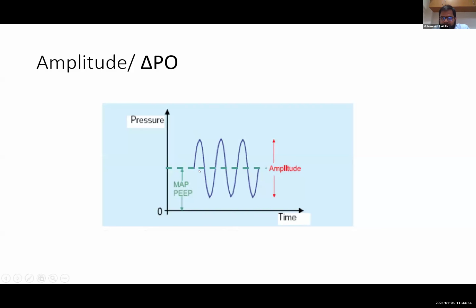depending on the TI time, the negative pressures will be less. If the IE time is more, then this pressure might be less, the delivered pressure during the expiration. So this will determine your amplitude. But as you see, the amplitude which was generated at the ventilator.